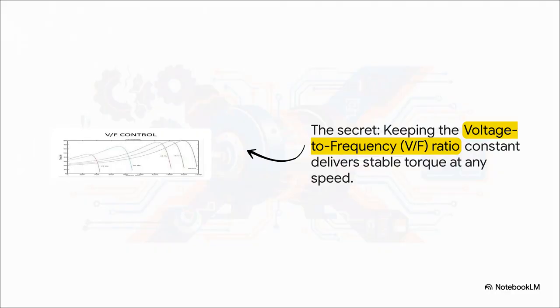So how does it do it? What's the secret sauce? It's actually this beautifully simple idea. The VFD's whole trick is to maintain a constant ratio between the voltage and the frequency it's sending to the motor. As it increases the frequency to make the motor spin faster, it also increases the voltage in lockstep. This constant V over F ratio keeps the motor's magnetic field strong and gives you stable, reliable torque no matter how fast or slow it's running.